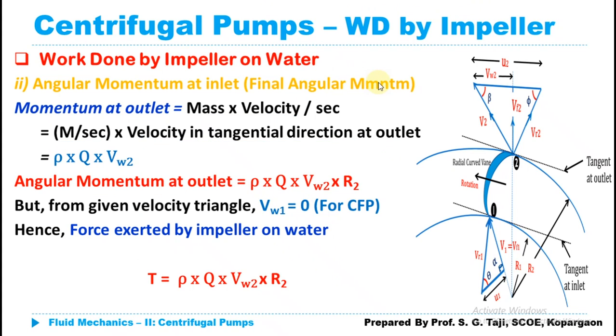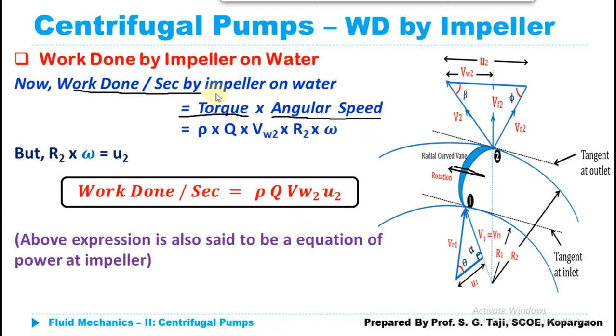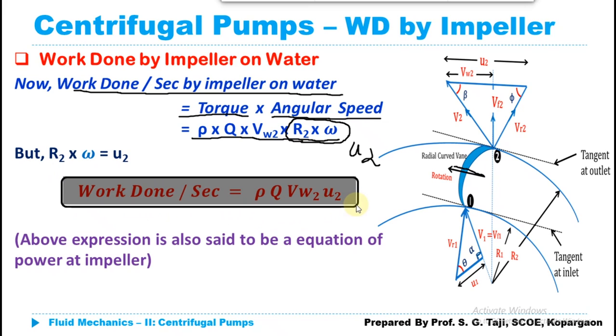Moving to the computation of work done per second: work done per second equals torque multiplied by angular speed Omega. So work done per second = ρQ × Vw2 × R2 × Omega. Since R2 × Omega = U2, this simplifies to work done per second = ρQ × Vw2 × U2. This expression is also called the equation of power at the impeller.